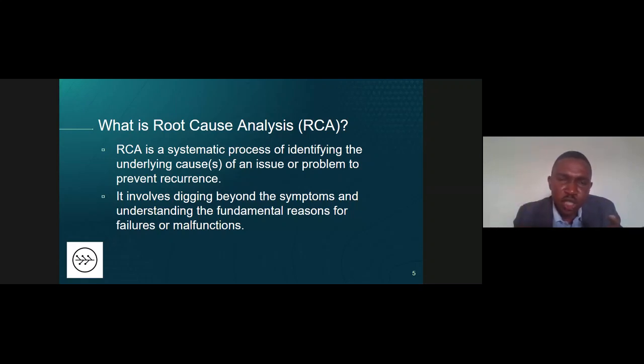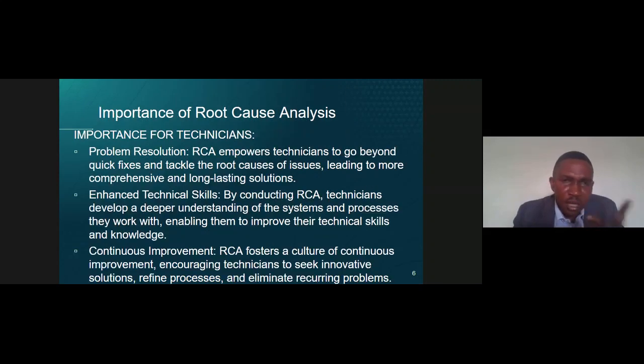But with root cause analysis, you want to find out what could cause that heat exchanger to have that leakage. Is it your process water? Is it your chemical water? Your chemistry of your water is not actually effective enough, so it's having a negative reaction to your heat exchanger. These are the things you have to find. So it is a systematic way of identifying it so that you eliminate the problem from occurring.